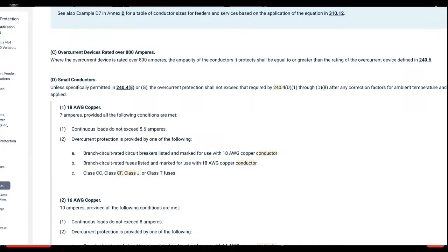It literally says the ampacity of the conductors it protects shall be equal to or greater than the rating of the overcurrent device. If you go up to 1,000, how is the overcurrent device equal to that? I don't see how 215.3 modifies anything in 240. No, it doesn't modify it, it literally tells you to go see Article 240, Part 1, and then look at the sizing of the overcurrent device. If you're over 800 amps, you drop down, because it has to be equal to or exceed the rating of the overcurrent device. So how can the device be 1,000 amps?